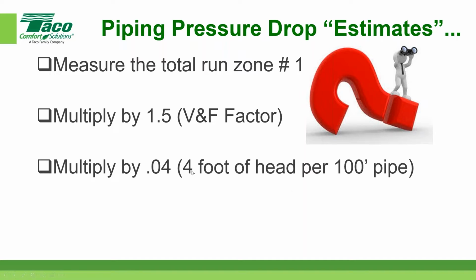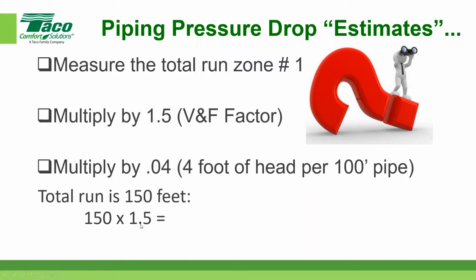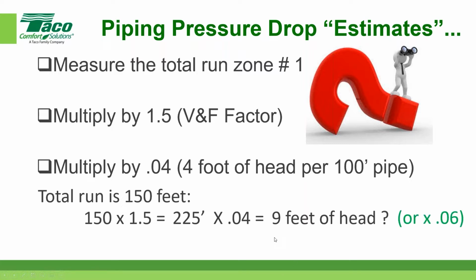Okay, so anyway, what we're saying here is you take this measured run. I'll do an example here. You multiply it by 1.5, then you multiply it by 0.04, and then you get your result. Let's say we measured 150. We take that times 1.5, that gives us 225, times 0.04, and by golly, it's 9 foot of head. Well, again, you can use that just as an estimate, but don't use it for actual pump sizing. It tends to oversize things pretty badly, actually. So here's another shortcut I'll show you. You can just take the 150 times 0.06. It'll give you the same number, because 1.5 times 0.04 is 0.06.